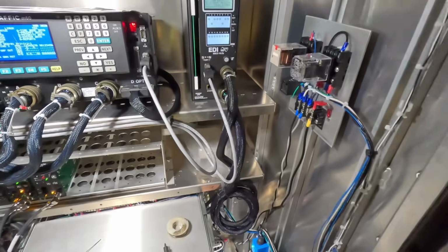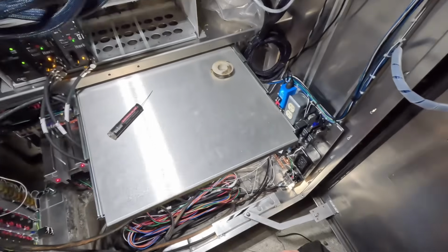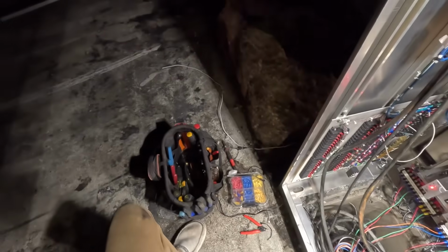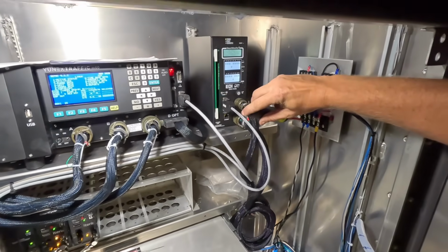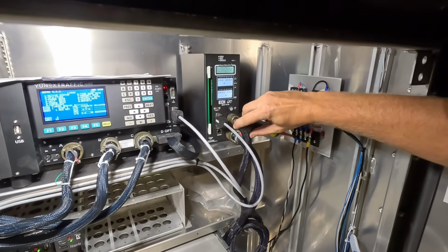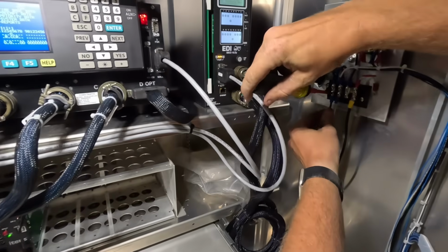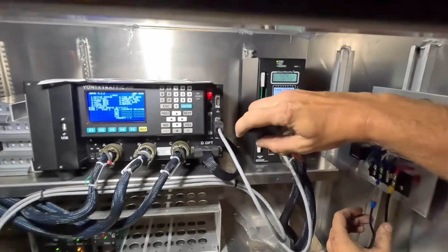Oh, you know what? Let me show y'all, dude, because I can show y'all. If I unland this cable, it will send it into that preempt mode. And let's not burn ourselves with this guy. Set it down over to the side for now. And then let me unland this cable, and I'll show you the preemption getting activated right away. And what would you know? Car's pulling up. Now there may be supplied voltage on this guy, but we're not gonna touch anything as we test it. Preempt 1's come on. We're green like it should be.